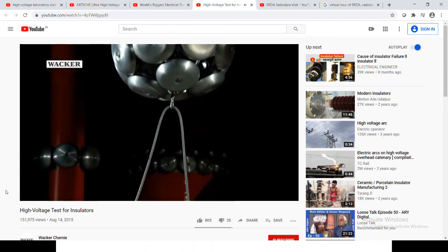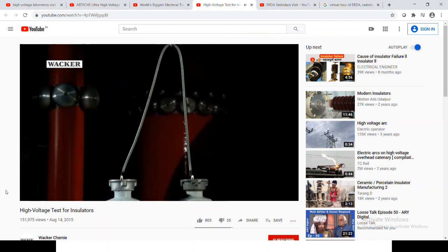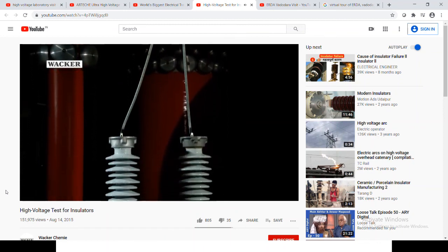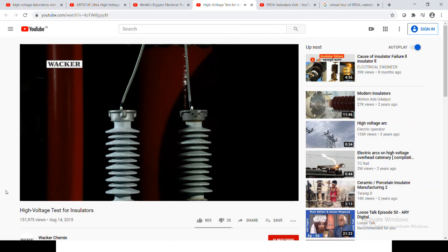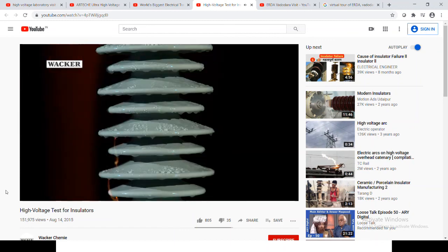The High Voltage Lab at Zittau University, Germany, tests the electrical resilience of insulators with and without PowerSil insulator coating. Uncoated porcelain insulators that are contaminated with a wet film layer are prone to electrical discharges, which can lead to flashovers.